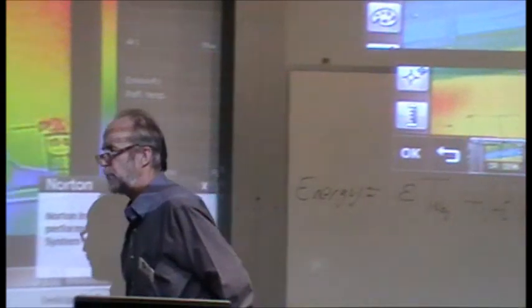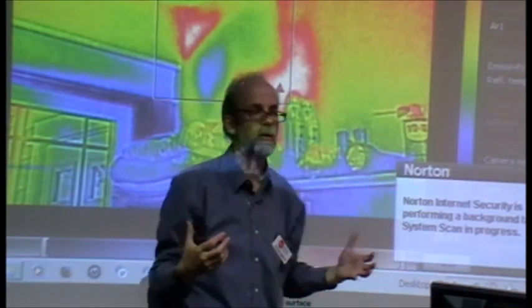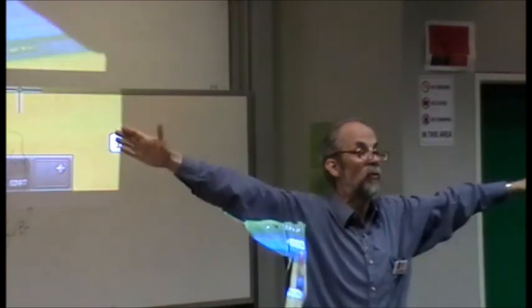The observation I'm going to come to now, perhaps a null, is that the inside of a big building like this is probably not a very good place to demonstrate the thermal imaging camera. You're better off going to the outside wall where you've got the leakage coming through and the hot sun outside. Certainly an internal room like this becomes quite problematic. But it's not impossible if you are able to control the environment. So if I'm looking for insulation breakdown between the rooms, leakage and so on, and we're able to air condition this space separate to what's outside, make it much hotter or much colder than what's outside, then I may be able to do something.